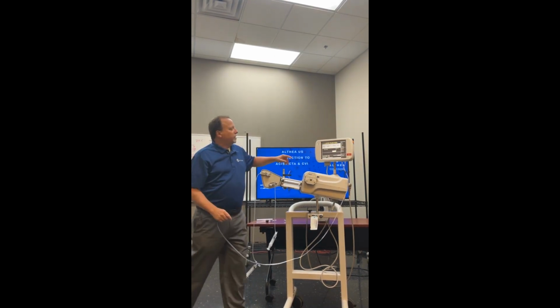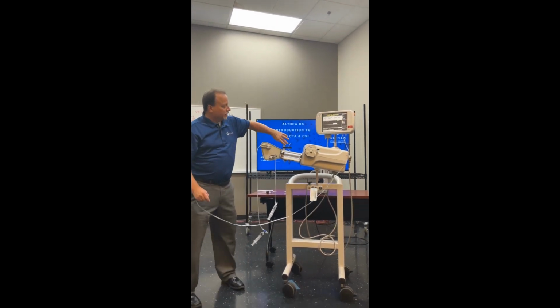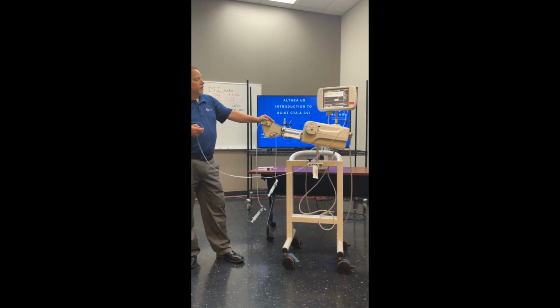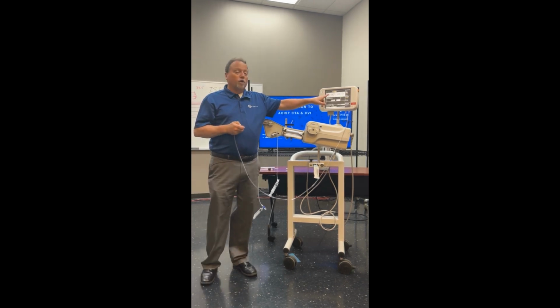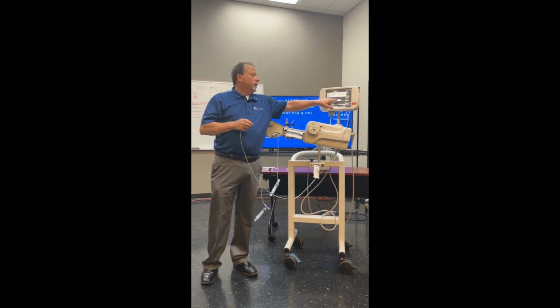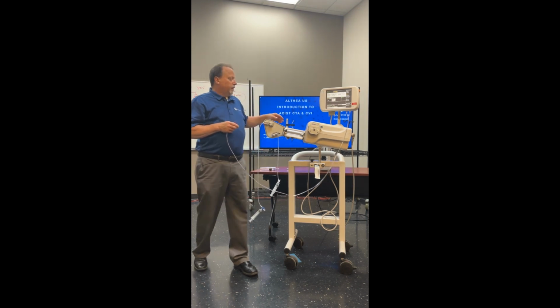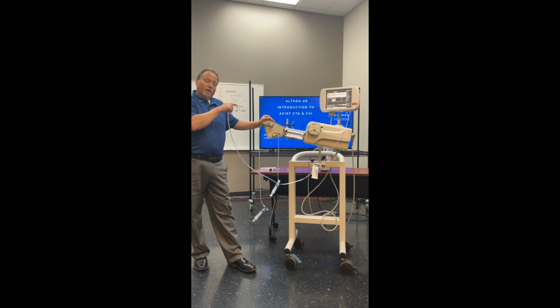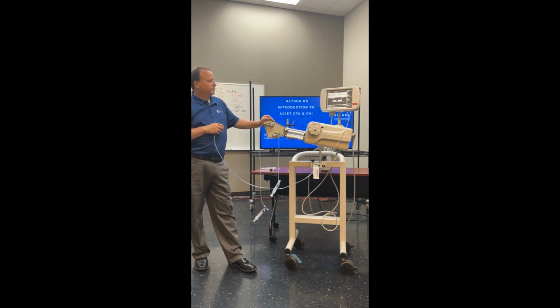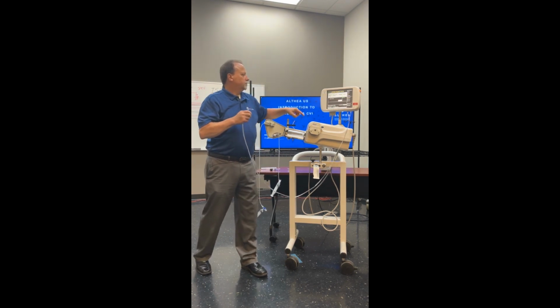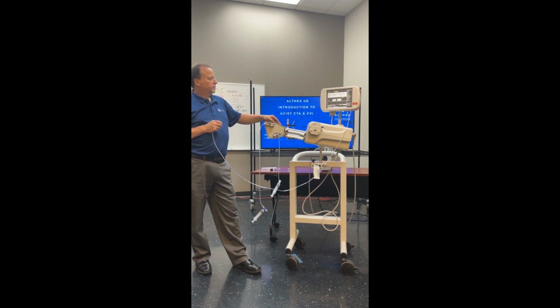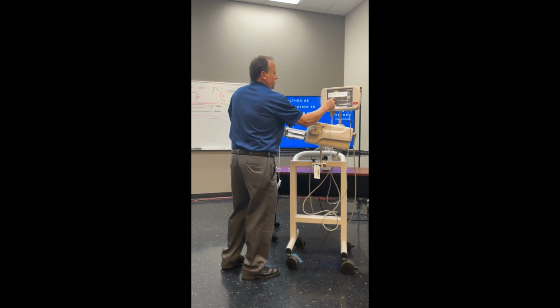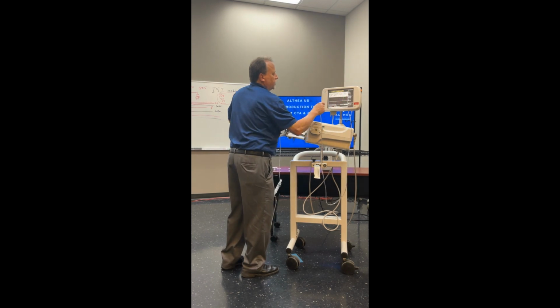And as you can see, it's flashing back and forth. And if we had lower lights, you would see that the back light here is flashing also. So I'm going to go ahead and inject. With a large injection, every time I let go of the hand switch, it's going to say okay to ARM. Now it's refilling back to 90 because I didn't have enough to inject. And we're going to go back to the low injection again.